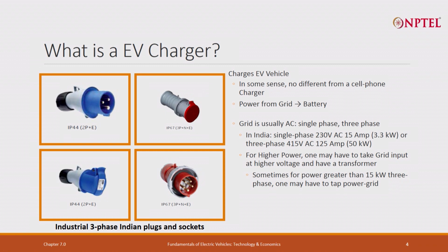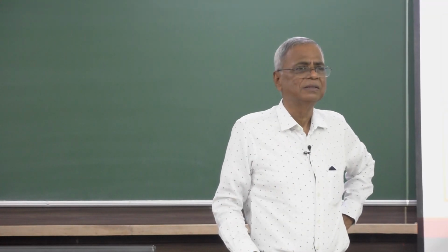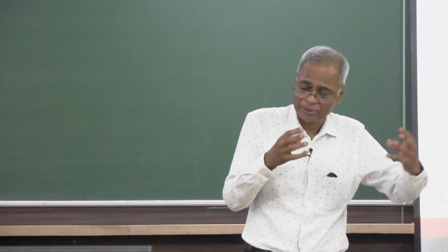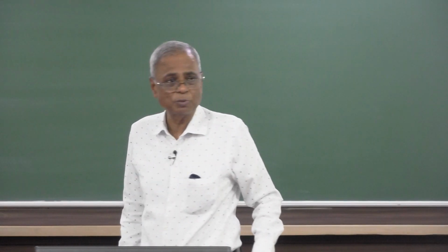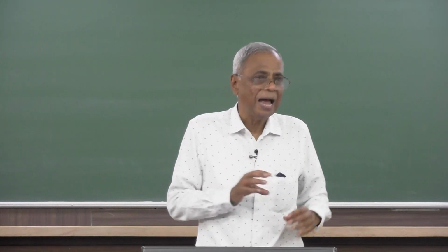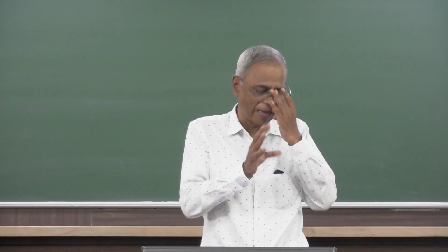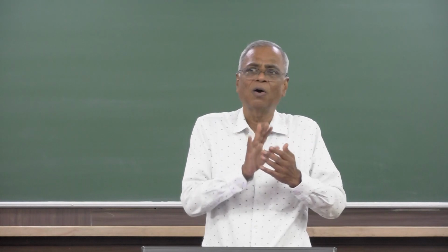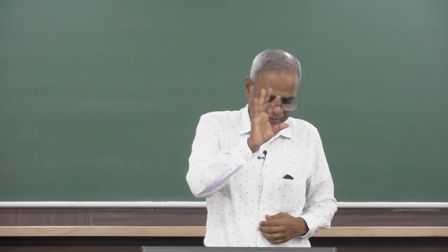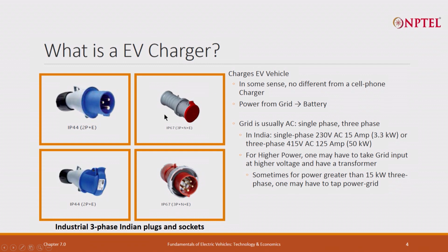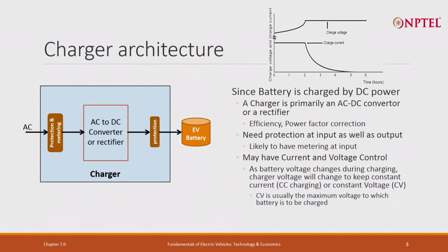Now why industrial? Because you are going to plug it in and take it out many times, 2,000 to 3,000 times. The socket and the plug both have to be reliable. Therefore special designs exist for reliability, and they can also stay connected securely. These are 3 phase, and normally they are rated IP67, which basically means rain can fall and whatever happens, it won't disturb the connection. So these are the single phase and three phase plugs and sockets that are used.